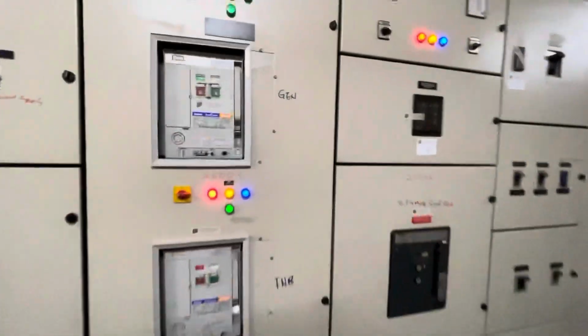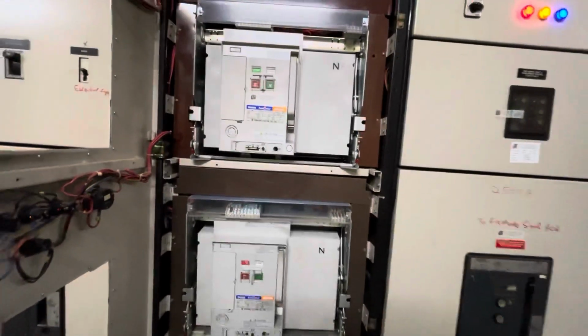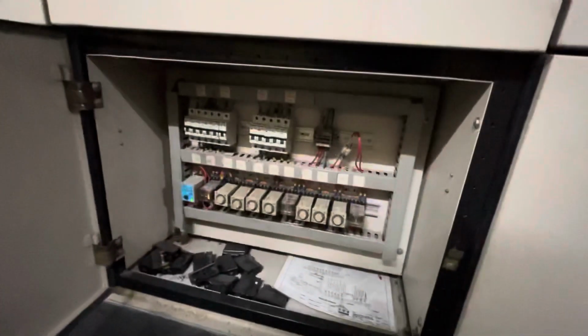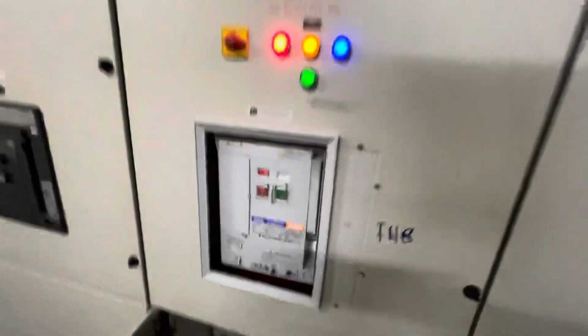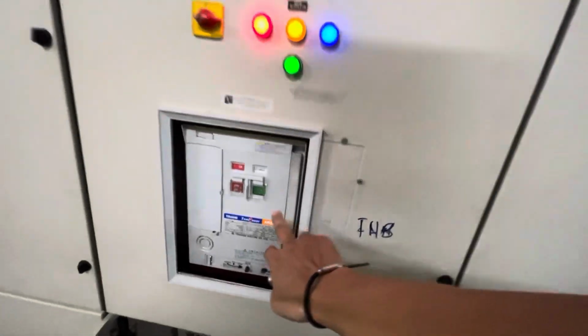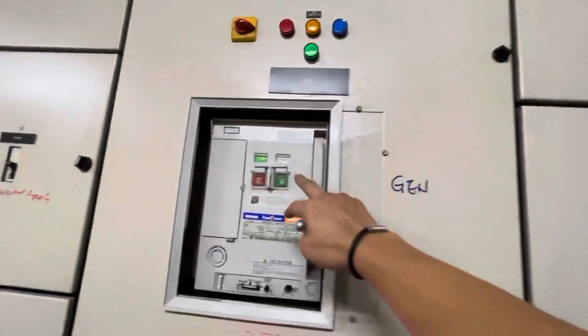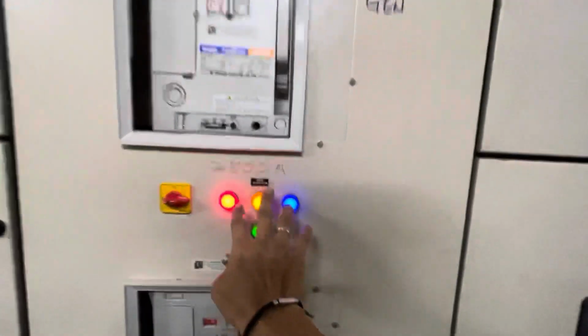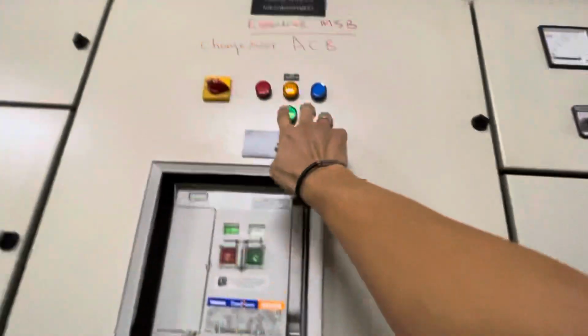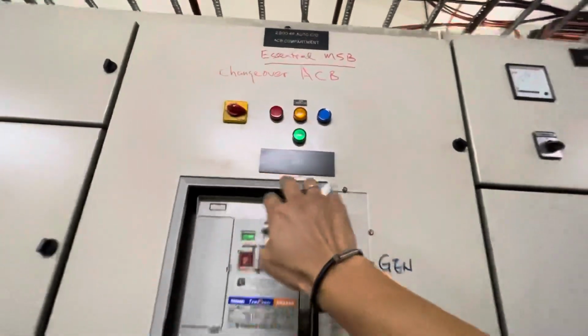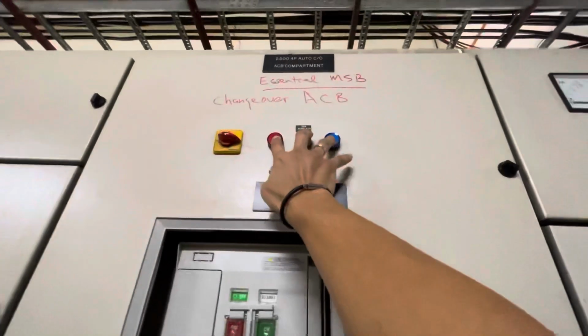Here we have the changeover ACB. This is using Terasaki brand. It's a 4-pole ACB, and the control panel is here for the ATS. Currently the genset is not in operation, so that's why you can see the TNB ACB is on, the genset ACB is off. This is the main supply and this is the genset supply. Once the genset is running, this light will light up.